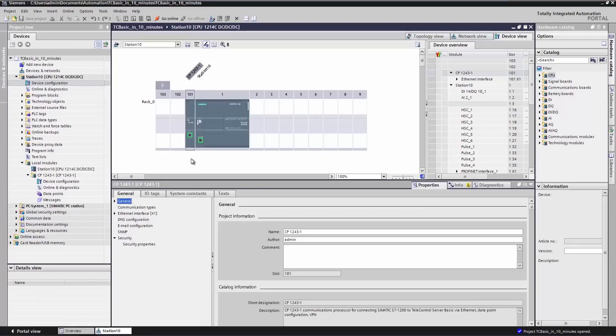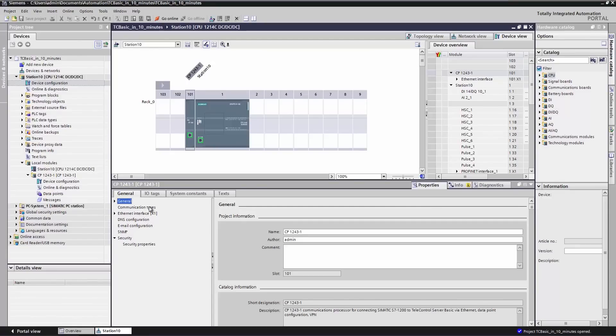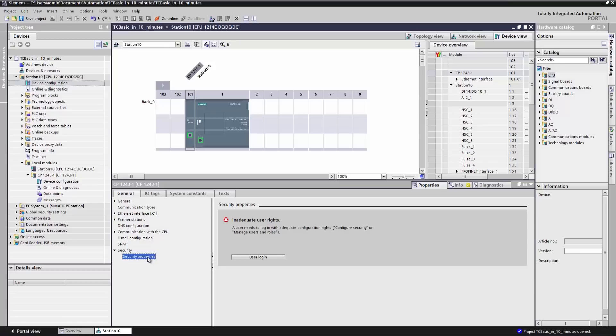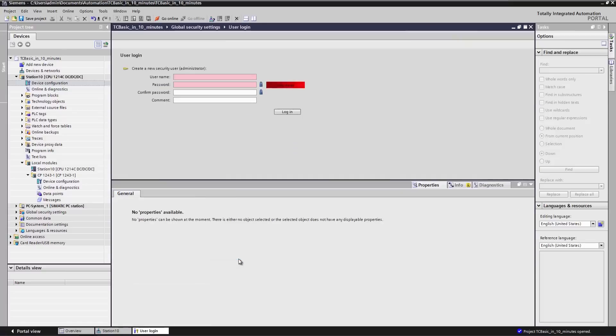Our station has already been created. It consists of an S7-1200 and a CP1243-1. We first activate the operating mode Telecontrol to make it possible for the CP to establish a connection to the Telecontrol Server BASIC. Because the CP creates an encrypted connection to the Telecontrol Server BASIC, we require the safety functions of the CP. For this purpose, we first specify a login ID and a password.